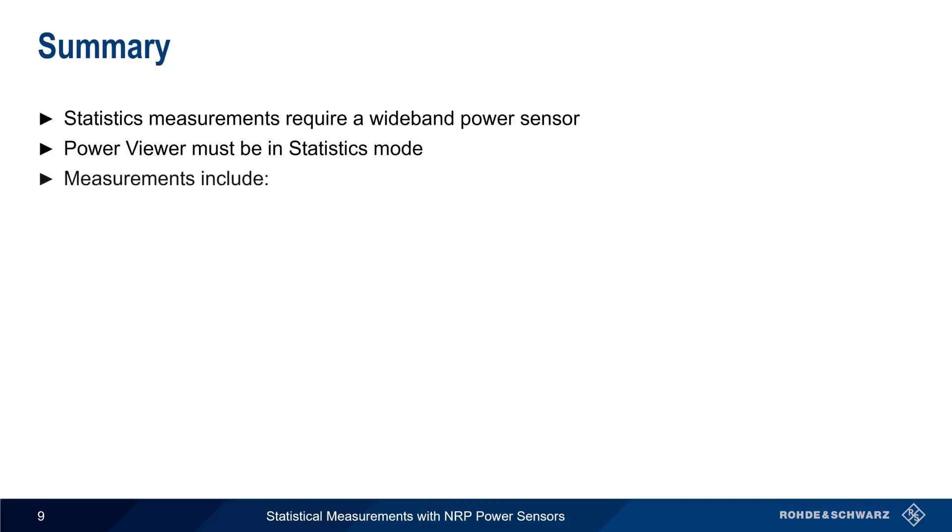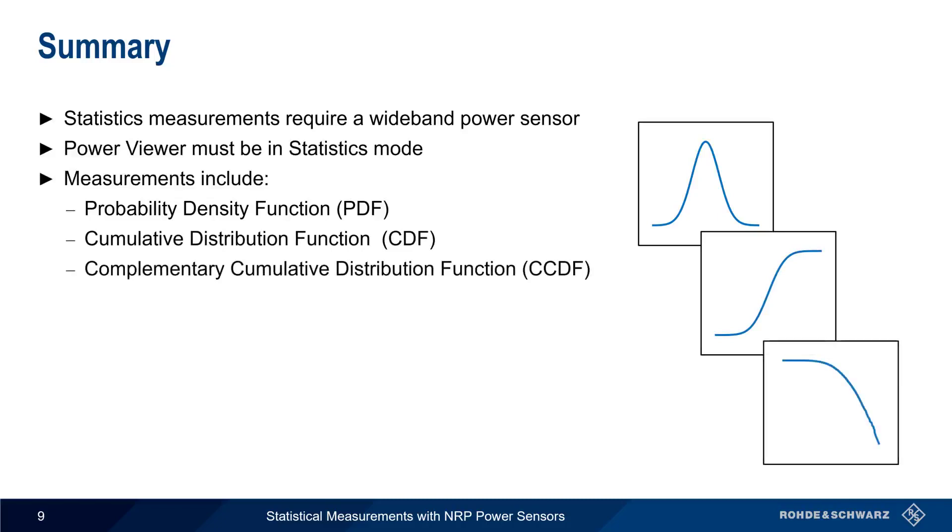Let's end with a brief summary. Statistical measurements require the use of a wideband power sensor, such as the NRP Z8x series. And in order to make statistical measurements, PowerViewer must be running in statistics mode. The three supported measurements are the probability density function, the cumulative distribution function, and the complementary cumulative distribution function, or CCDF.